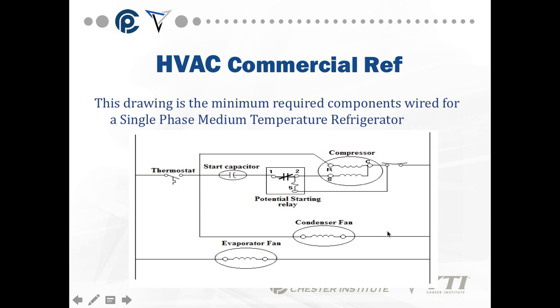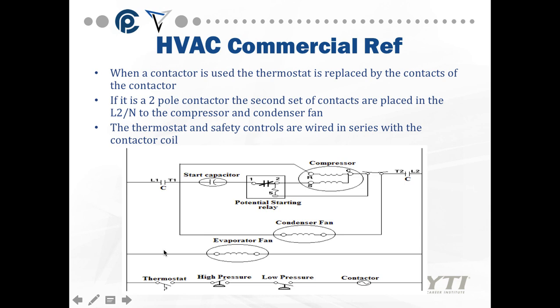At the same time, we energize my condenser fan, evaporator fan — and in a commercial system it runs constantly. When the contactor is used, the thermostat is replaced by the contacts of the contactor. If it has two-pole contacts, the second set of contacts are placed on the L2 neutral to the condenser and the compressor. The thermostat and safety controls are wired in series with the contactor coil. The evaporator fan runs constantly.